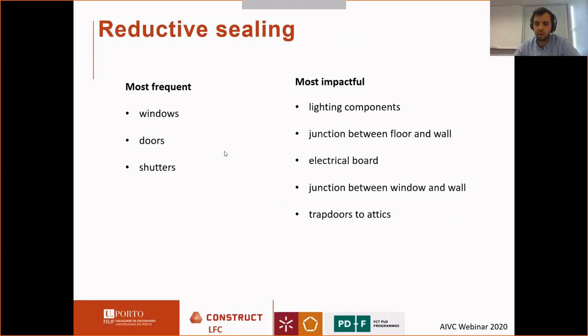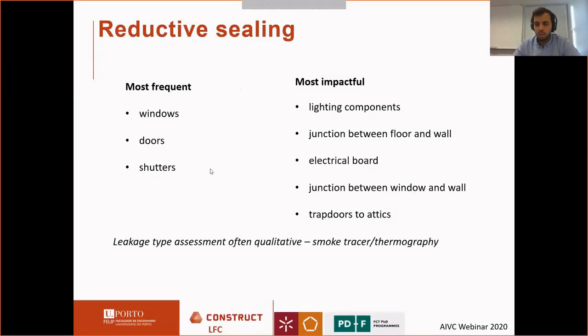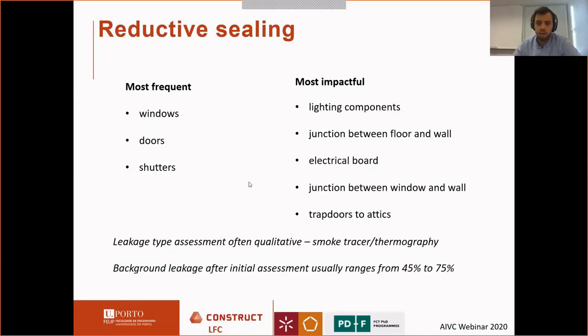From several publications, the most frequent leakage paths are windows, doors, and shutters, but these are not the most impactful. The most impactful range from lighting components, junctions between floors, electrical boards, and some trapdoors to attics. Normally this leakage assessment is qualitative — either by thermal imaging or smoke — and not quite quantitative. Studies that provide quantitative assessments show that the background leakage after initial assessment ranges from 45 to 75 percent.